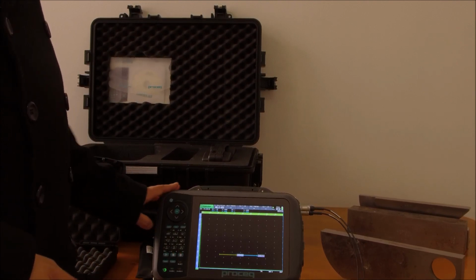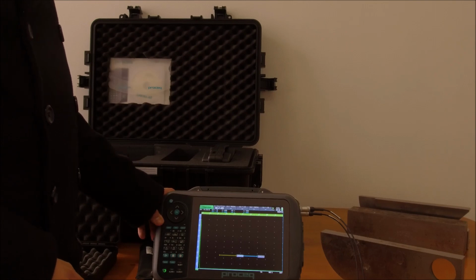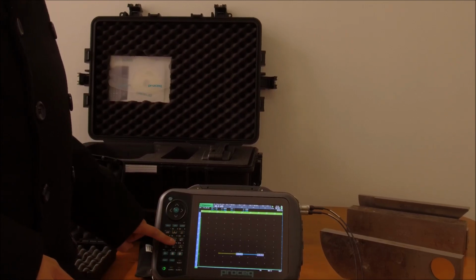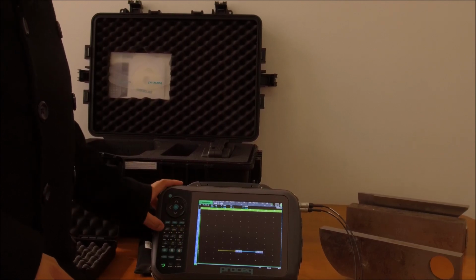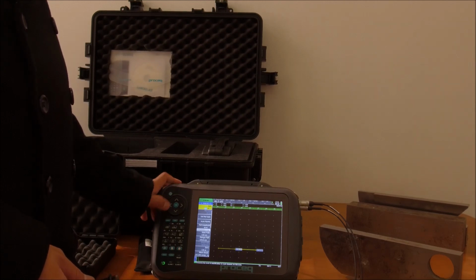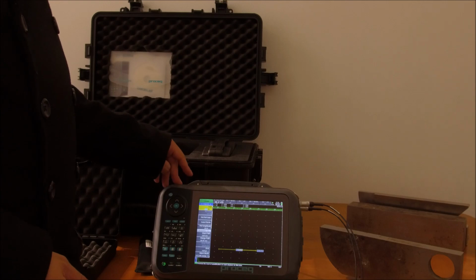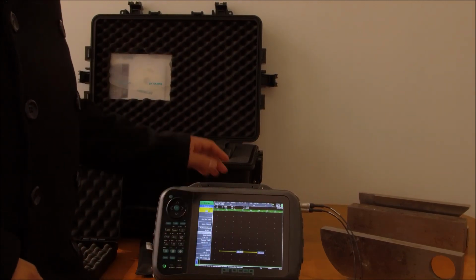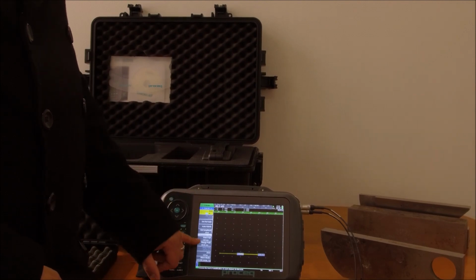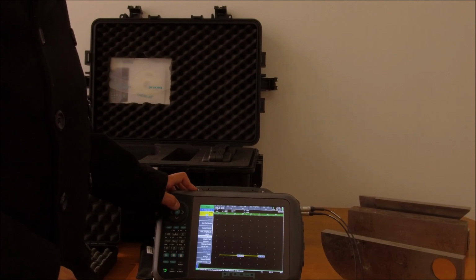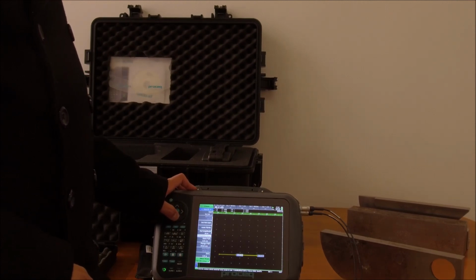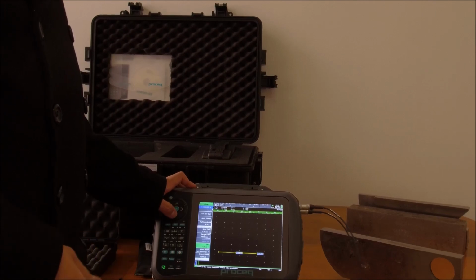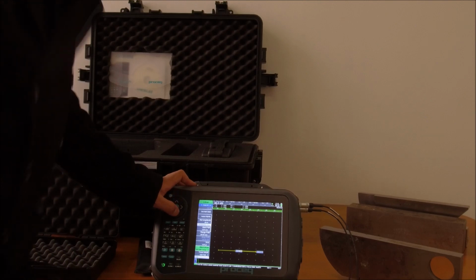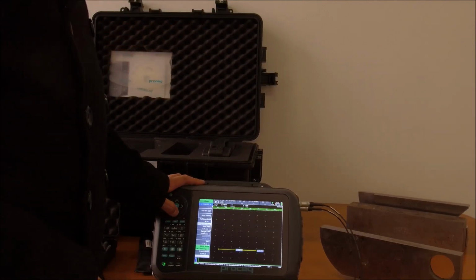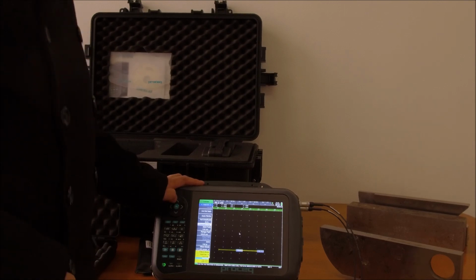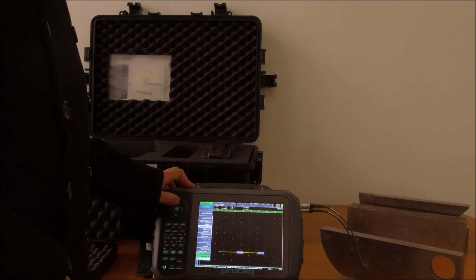So that's what it looks like when we're in action. A couple of things. Down the side here, we have 6 shortcut buttons. dB relates to your gain, so we can set things like our current gain and our reference gain. We can auto full screen height, so whatever is selected by our gate will auto full screen height. We can set up paths, so our range and whatnot. We can also set things like 0, so this is our 0 offset. We can set our wave mode, so we've got it at longitudinal wave 5890. Travel mode: half path, full time, half time. So you can put that down however you like.